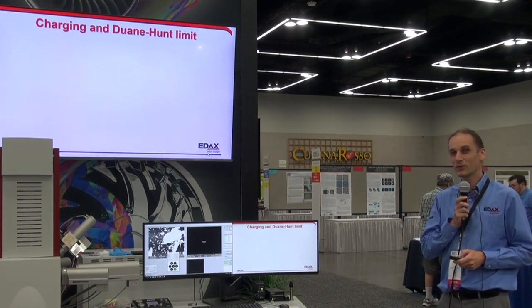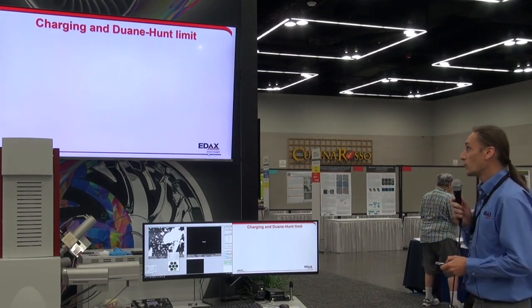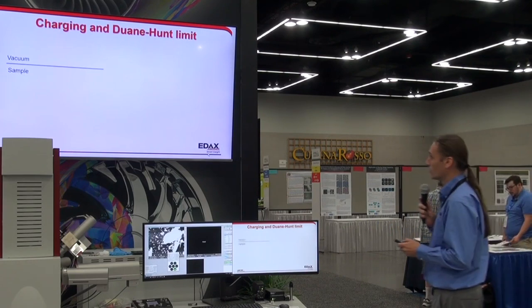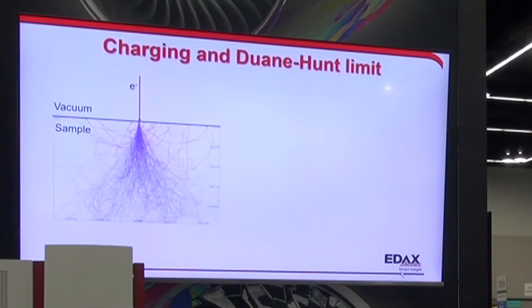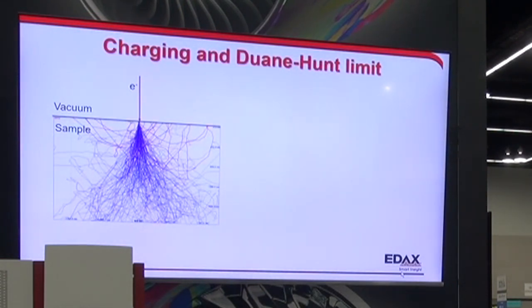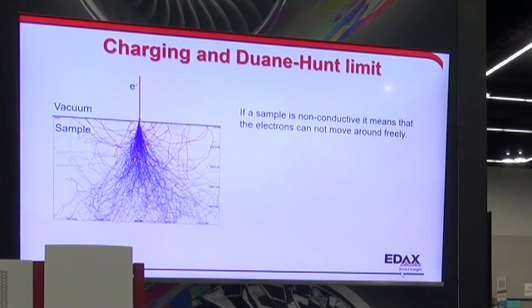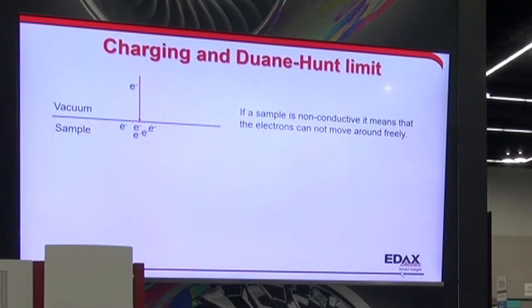However, the acceleration voltage and the cutoff don't always coincide. If we have charging samples, what happens is we put electrons down into non-conductive samples. Normally the electrons would scatter around and drain out through the stage, but a non-conductive or charging sample means the electrons can't flow freely. Instead of draining out through the stage, we have a buildup of electrons on the sample.